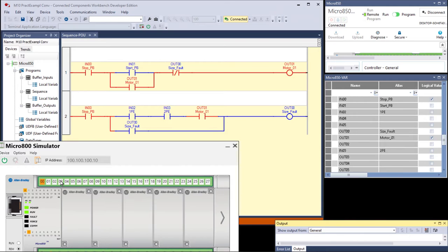However, if we go back, another carton comes in, and it could even be skewed. I mentioned earlier, if the carton was skewed, you wanted enough space between the optical paths or the photo eyes that it wouldn't allow a skewed carton to block both. I changed my mind. If the carton is that crooked, we don't want it continuing on down the conveyor. And honestly, it should not be crooked, because when it rolled down the gravity conveyor and struck the leading edge of the first conveyor, running or not, it should have squared it up. We'll just say that a skewed small carton or a rogue carton, a larger one, could cause this condition.